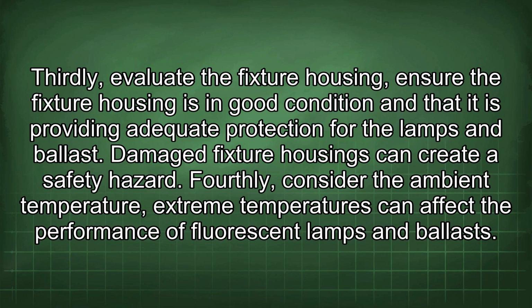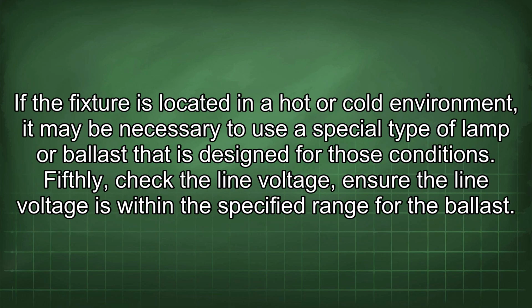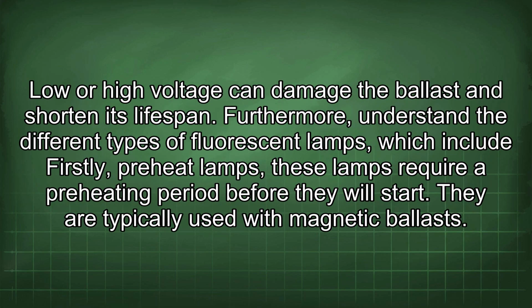Fourthly, consider the ambient temperature. Extreme temperatures can affect the performance of fluorescent lamps and ballasts. If the fixture is located in a hot or cold environment, it may be necessary to use a special type of lamp or ballast that is designed for those conditions. Fifthly, check the line voltage. Ensure the line voltage is within the specified range for the ballast. Low or high voltage can damage the ballast and shorten its lifespan.